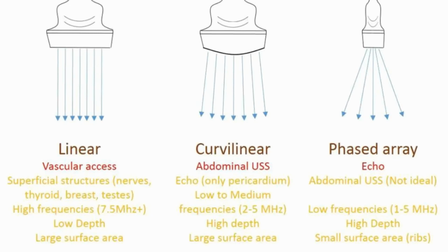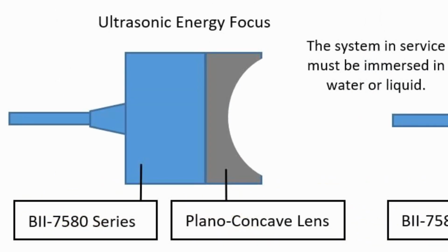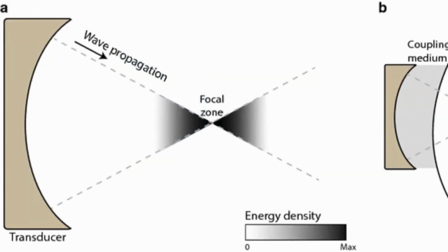Ultrasounds that are used for sonography have a fixed focus, meaning that the focal point cannot be synthetically produced. In a transducer, the focal point is usually determined by the style of lens in front of the piezoelectric crystals. For the transducers to create a focal point, a concave lens is put in front of the array of crystals so that when the ultrasound beam is transmitted, it produces a fixed focal point.